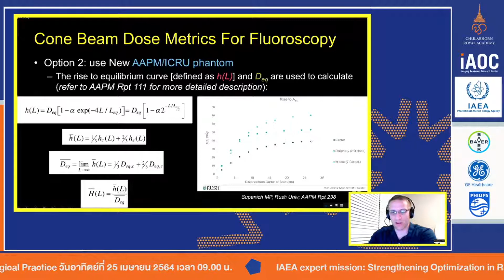So if you use just a simple CTDI phantom that's 15 centimeters thick or wide, and then you have either the 32 centimeter diameter or the 16 centimeter diameter, you can see that those only approximate roughly 50% to 87 to 90% of the actual dose being delivered in the area of the cone beam CT. So they highly underestimate the amount of dose coming out of your system into this area that it's imaging. But if you know what your equilibrium dose is at the center and at the periphery, you know what the total dose is to that area. So that's the reason why we're doing all this.